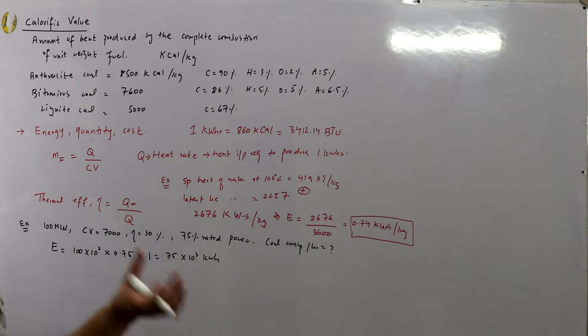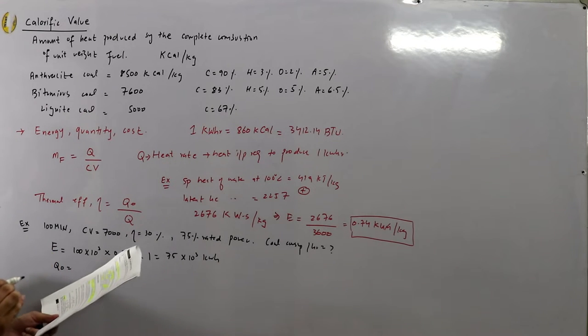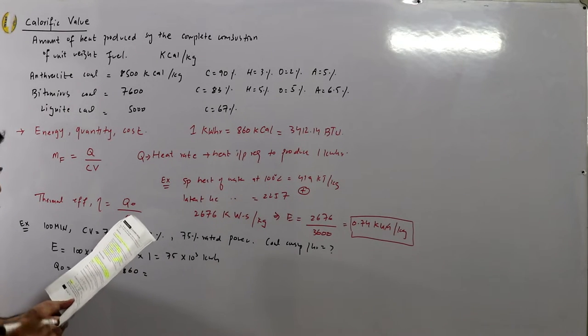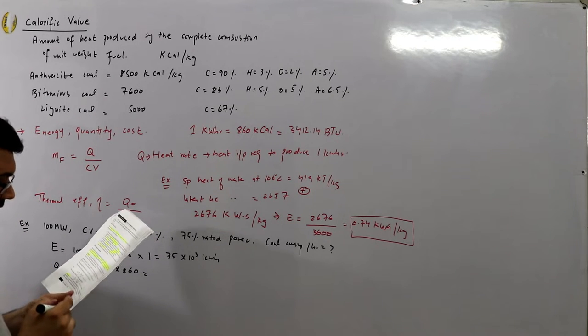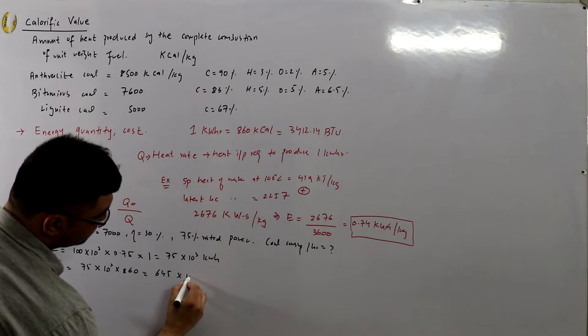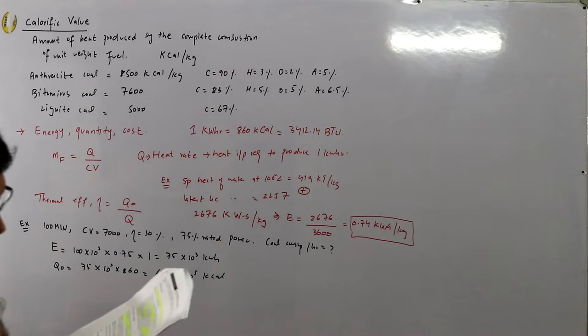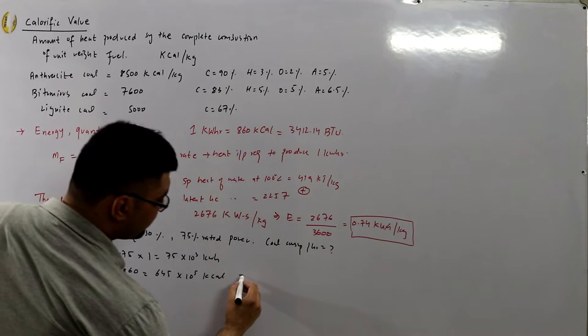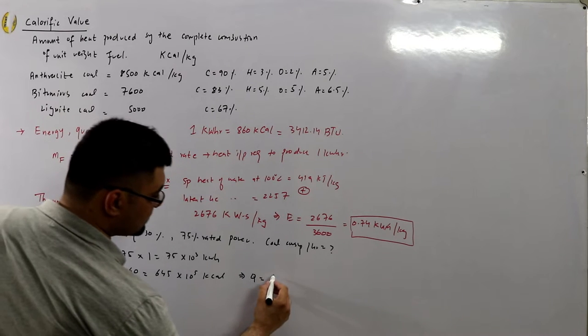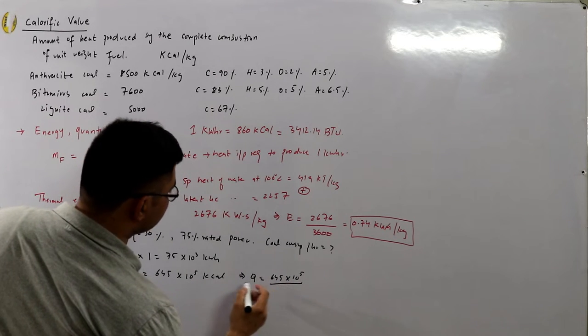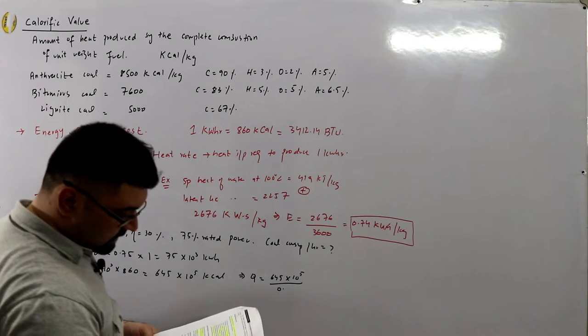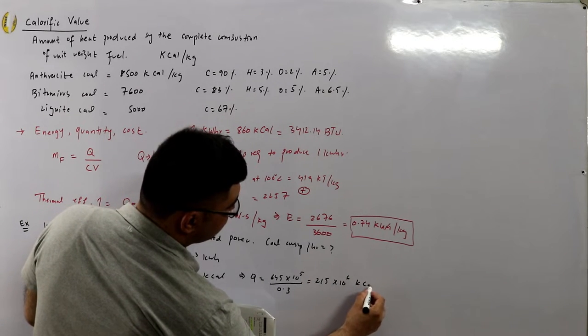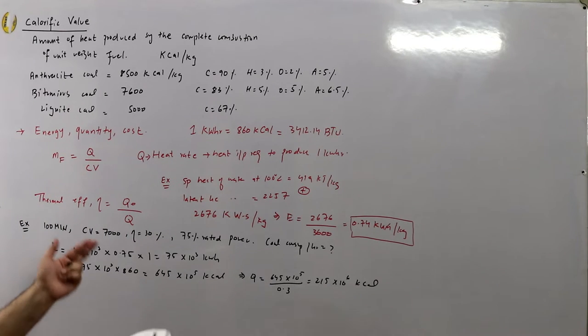Convert electrical energy to heat equivalent: Q₀ = 75×10³ × 860 = 645×10⁵ kilocalories. Using overall efficiency of 30%, find heat input Q: Q = Q₀ / η = 645×10⁵ / 0.3 = 215×10⁶ kilocalories. This is the heat input required.